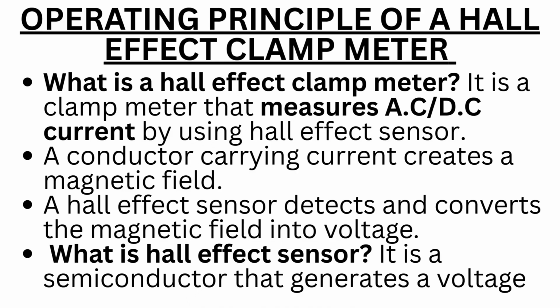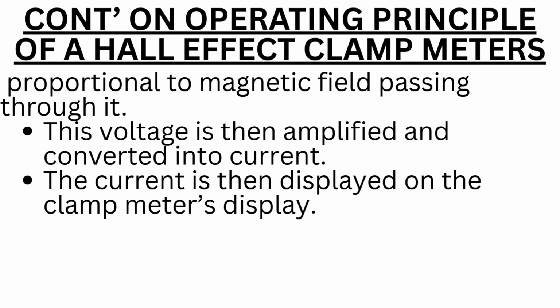Now let us look at the operating principle of a Hall effect clamp meter. But first, what is a Hall effect clamp meter? It is a clamp meter that measures AC or DC current by using a Hall effect sensor. A conductor carrying current creates a magnetic field. A Hall effect sensor detects and converts the magnetic field into voltage. What is a Hall effect sensor? It is a semiconductor that generates a voltage proportional to the magnetic field passing through it. This voltage is then amplified and converted into current. The current is then displayed on the clamp meter's display.